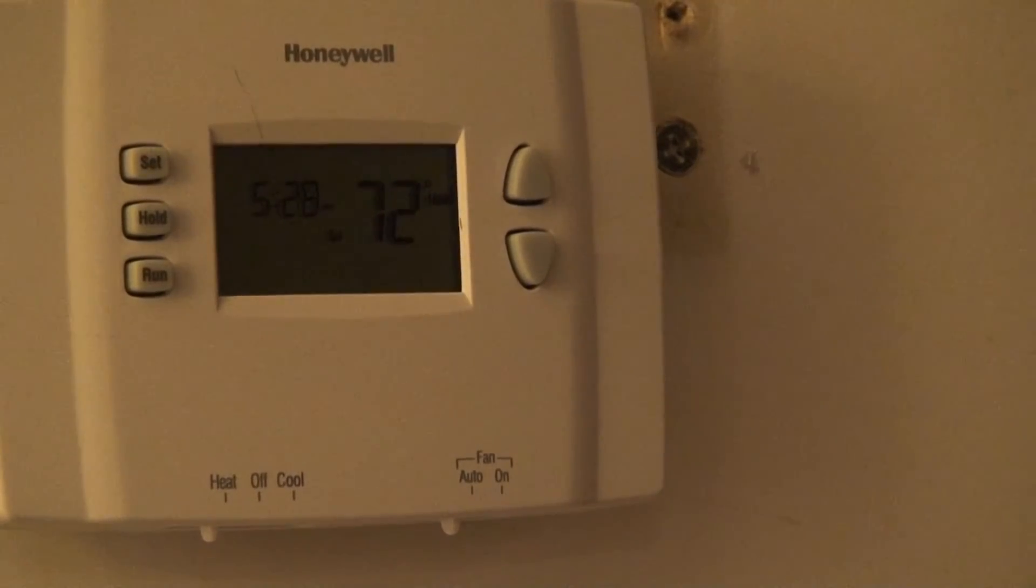If it reached 72, then obviously the other thermostat was bad too, probably because it got paint on it so it wasn't reading the full temperature. Because it was reading 68 in here, this one's reading at 72.